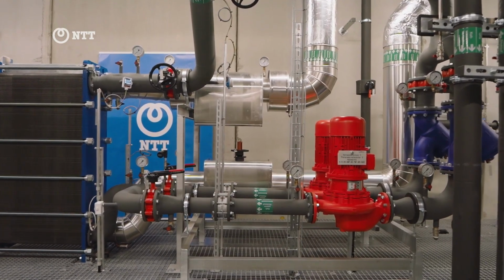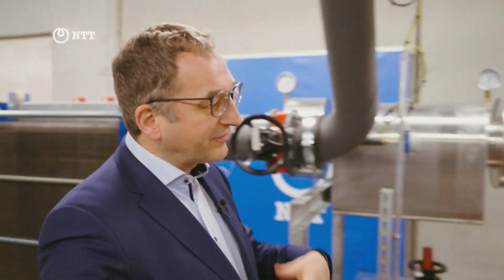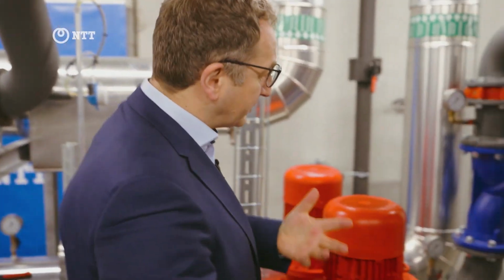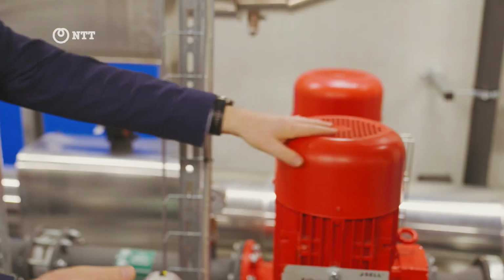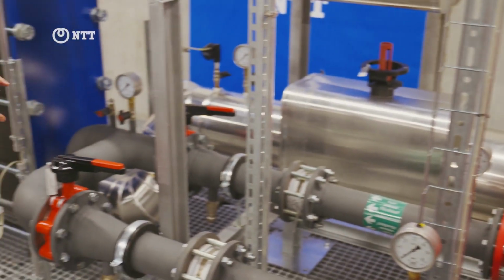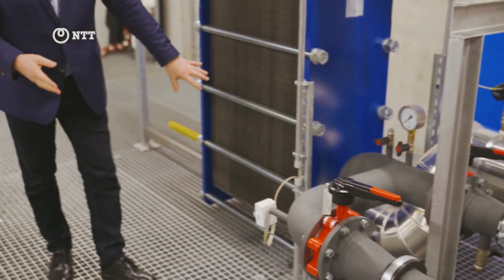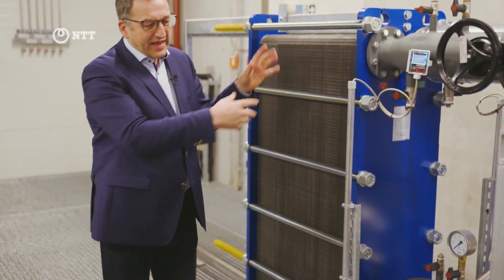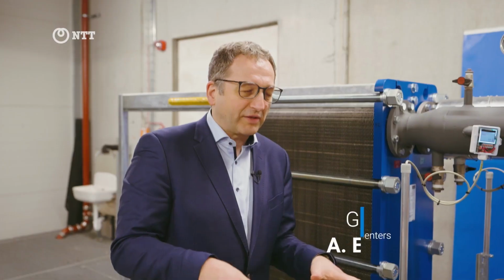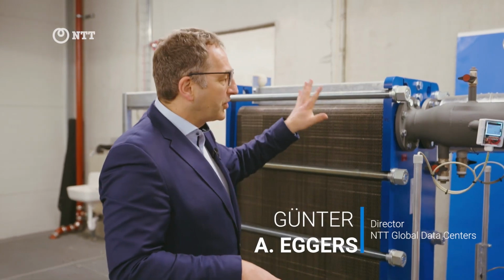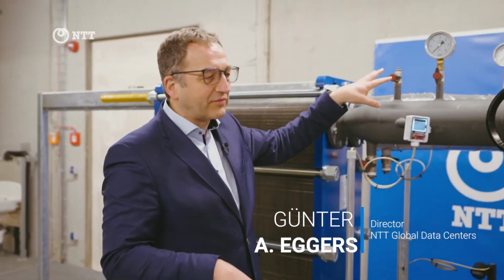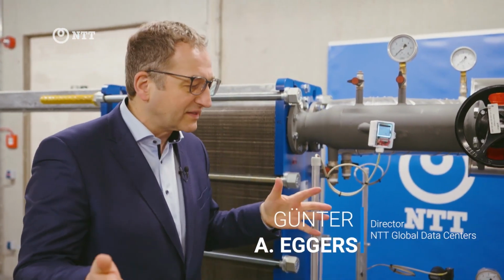How does it really work? The hot water coming from the IT equipment, which we're cooling downstairs, comes through these pipes, driven by these pumps, going to the bottom of this heat exchanger. The temperature will be something like 30 degrees Celsius, and that will be cooled in the heat exchanger to 20 degrees Celsius - a difference of maybe 10 degrees.